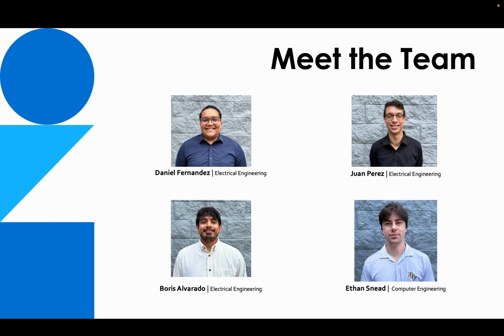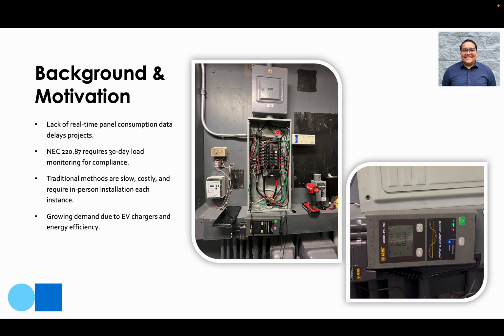Currently, if a new load is being added into a panel, such as an EV charger, the existing requirement based on the National Electrical Code 220.87 is that we have a load study of the panel, or an exception to this rule is that we can provide 30-day load monitoring from the panel.